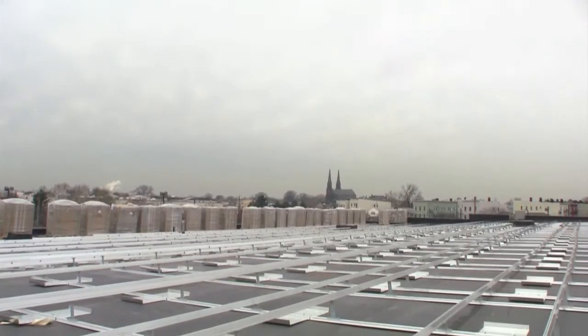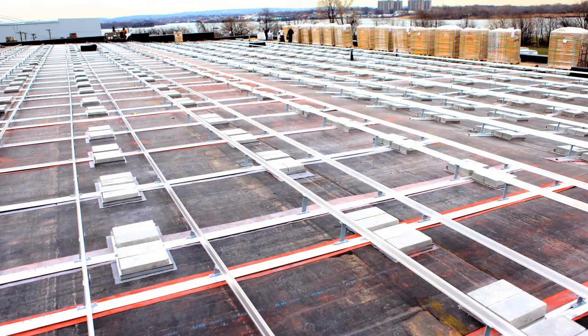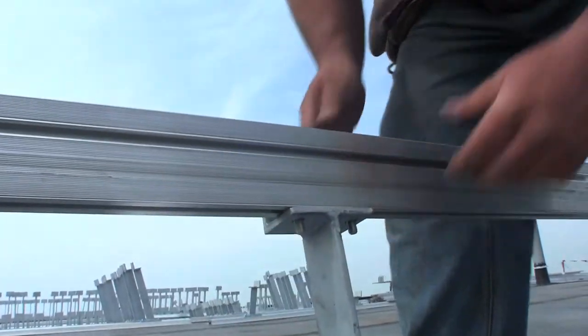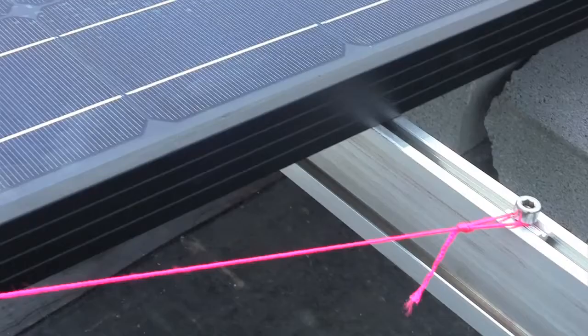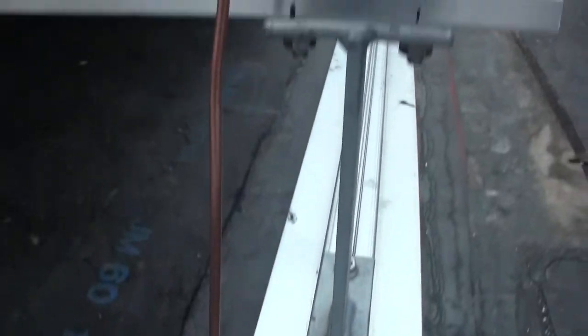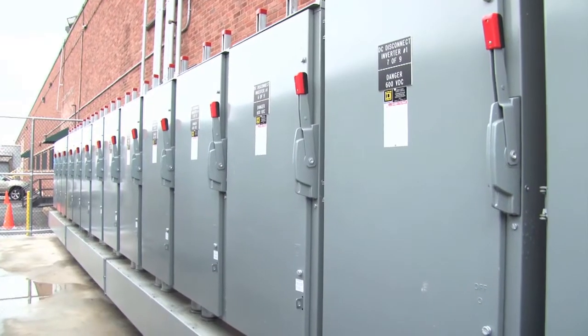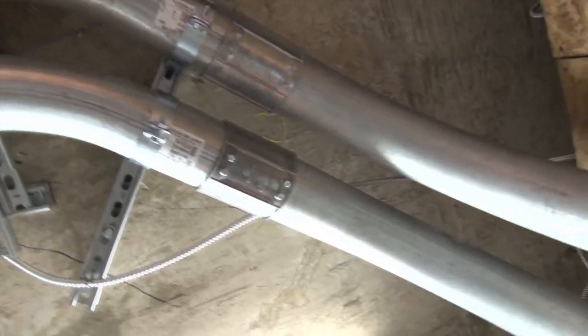Being a flat roof install, the Geoscape Solar engineers chose to use a non-puncturing flat ballast pan system using a total of 8,800 cinder blocks to secure the racking and panels to the roof. An aluminum racking system was installed, followed by 4,072 panels, which had to be leveled, grounded, and finally connected to the relay boxes which send the electricity to the inverters.